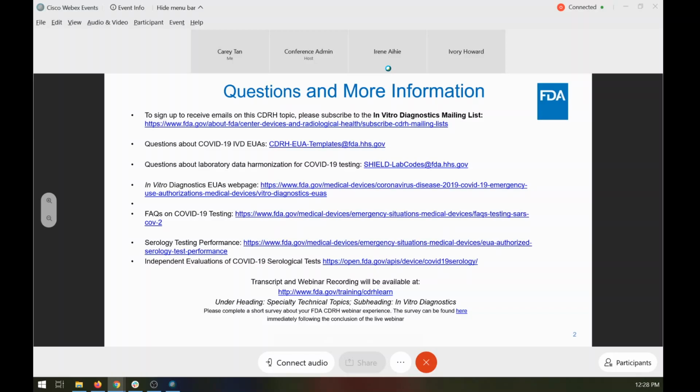Hello, this is Savannah Estes, also from UserWise. My question is regarding home use usability testing. The FDA recommended us to evaluate the labeling and instructions for a test kit using a multiple choice questionnaire, but historically our human factors community has found that multiple choice questions are inappropriate for assessing comprehension of labeling. And so we always ask these questions directly to participants and rarely have them fill out forms themselves. Has the FDA human factors team confirmed that multiple choice questions for home use human factors testing is the most effective way to assess labeling IFUs?